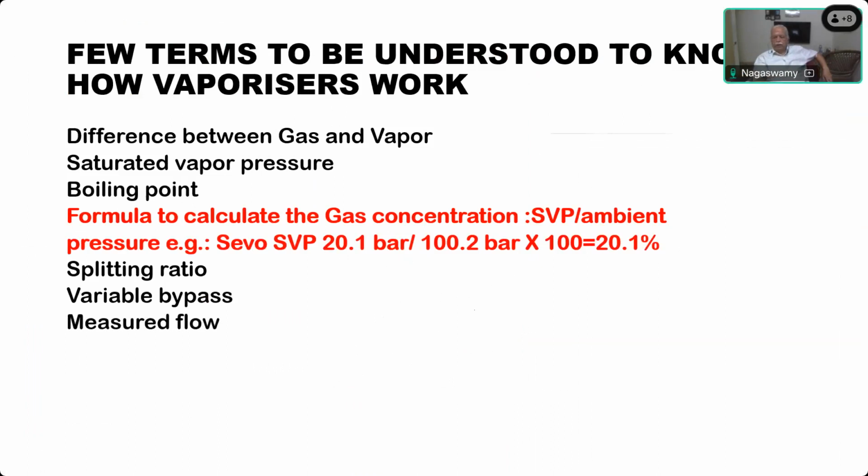One vaporizer which you are using in the modern day is a measured flow vaporizer. Which one is that? Desflurane. Desflurane, yes. Why is there so much hesitation? Desflurane vaporizer is a measured flow vaporizer where the fresh gas flow does not totally enter into the vaporizing chamber.